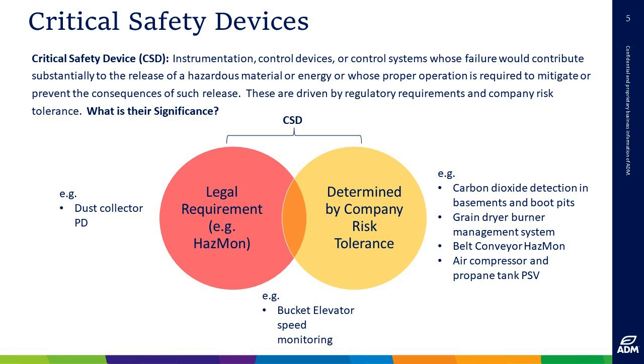That's required, at least in the US, in 1910-272. So even though that might not necessarily be something one would think of as dangerous if our magnehelic goes down, well, maybe it is, maybe it isn't, but it is legally required. So for us, that would be considered a CSD. This is a license to operate. This device must be functional for us to have a license to operate.